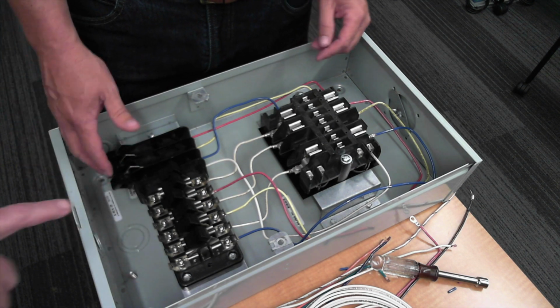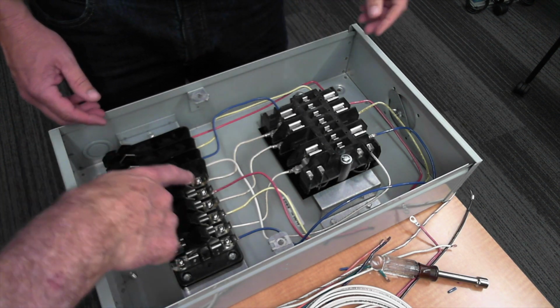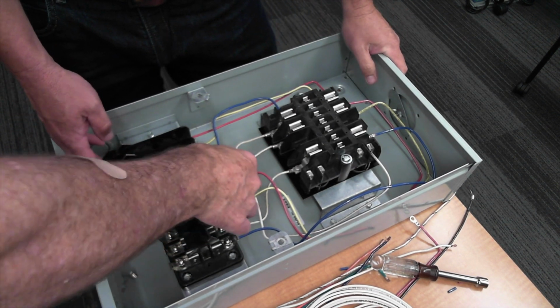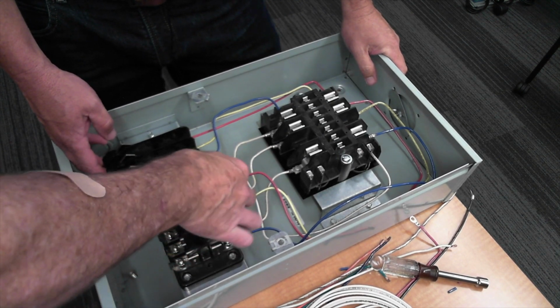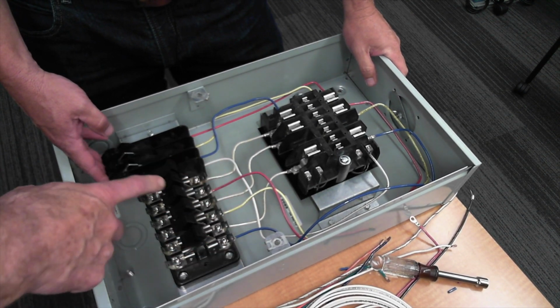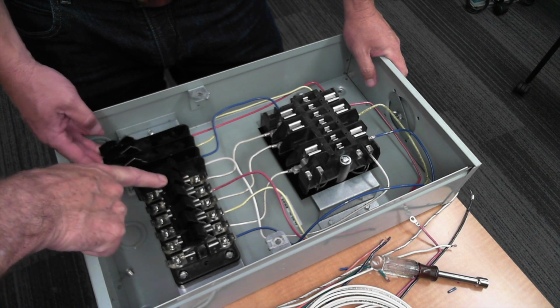That's for a drain, right. So it'll come in through here at the bottom, and then it'll come through the shunt blade. Because remember, when we're disconnecting and we open that, we disconnect the current, or shunt the current coming from the CT.